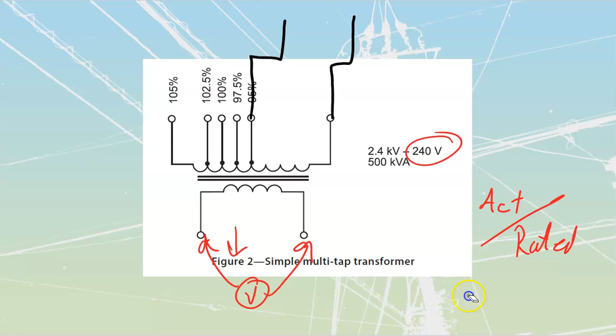What it is actually changing for us is the volts per turn, right? What I have up top here, this 2400 volts or whatever it's going to be, I guess it would have been 2200 volts with all my line drop. The 2200 volts, I had it over top of 100% of the turns. Now I'm going to drop it over top of 0.95 of the turns, which means we have a lot more volts per turn that are going to be induced onto the secondary side.